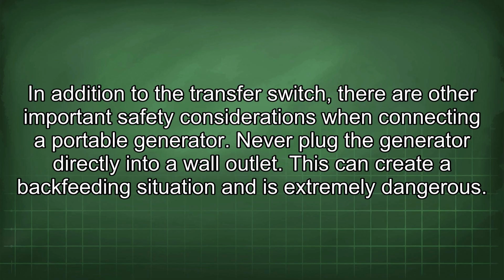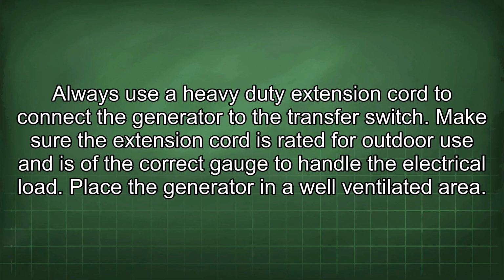Never plug the generator directly into a wall outlet. This can create a backfeeding situation and is extremely dangerous. Always use a heavy-duty extension cord to connect the generator to the transfer switch. Make sure the extension cord is rated for outdoor use and is of the correct gauge to handle the electrical load.